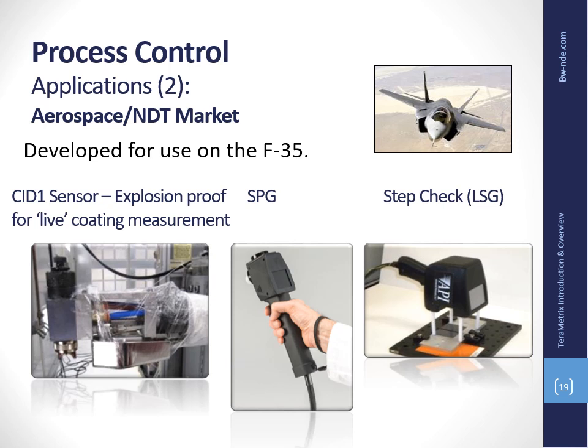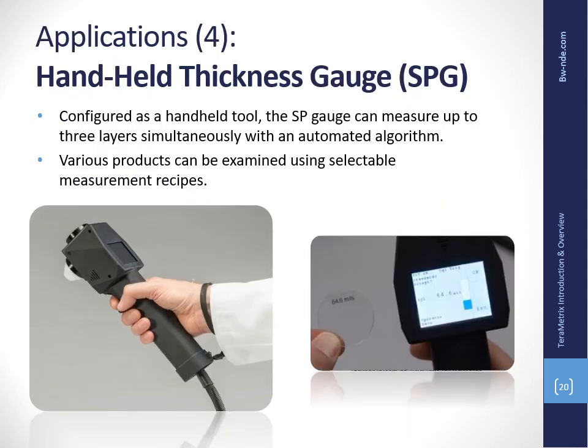The step check, which became the line scan gauge, was developed for measuring the accuracy of butt joints to ensure they were level and that the gap between plates was correct. The single point gauge is configured to allow the measurement of up to 3 layers simultaneously. Different recipes or programs can be selected to evaluate different products. The next video shows this being used for measurement of a 3-layer fuel tank.